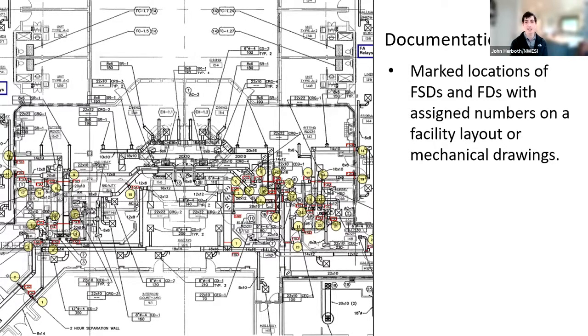The damage that can cause in a shaft or large equipment is definitely not something you want to risk on that first test. And so you have an option. Do you trip the fire alarm system by smoking a head? Or do you use a field disconnect? Or do you trip a breaker? Do you use the fire alarm panel to trip the whole system? It really depends on what type of building you're in.